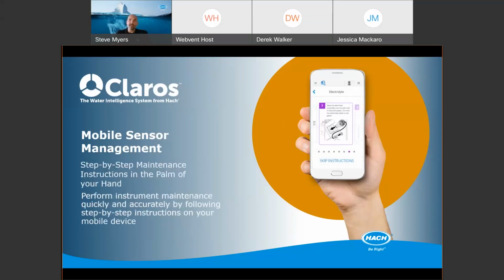A few ways that this is achieved is first, step-by-step visual procedures. So no need to go get the manual off the shelf, or even maybe set this up in the asset management system. It can do this proactively with alerts. And once the operator or instrument technician is out at the instrument, it can walk through with some detailed visuals of exactly what the step-by-step maintenance procedure looks like.